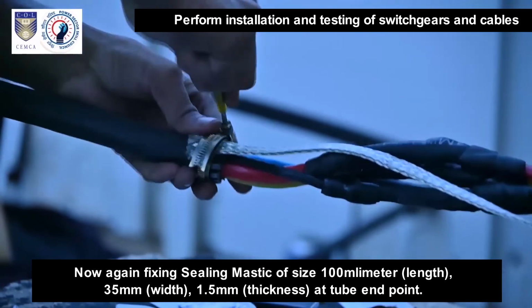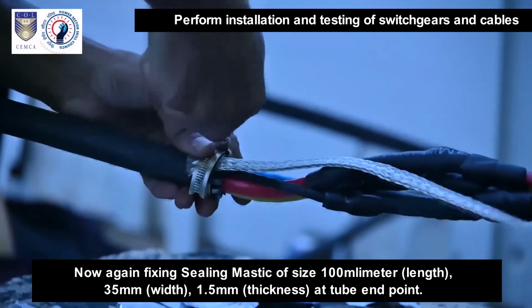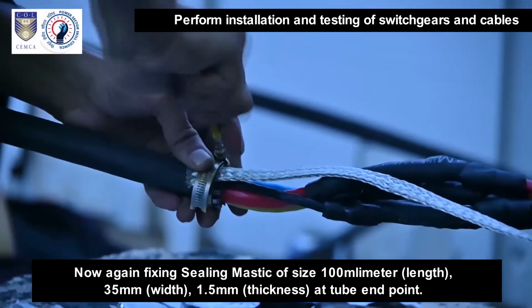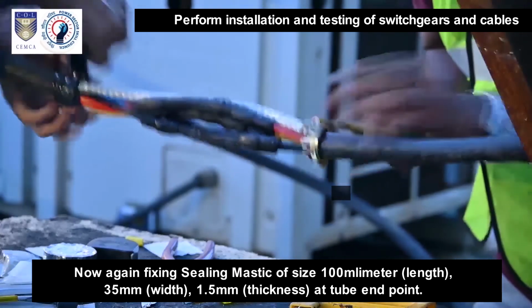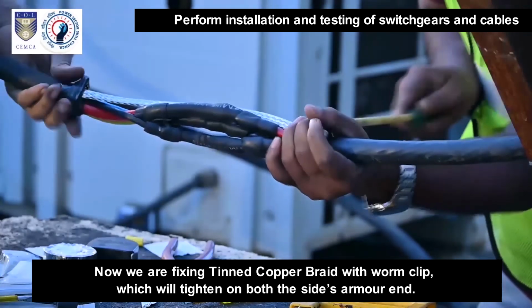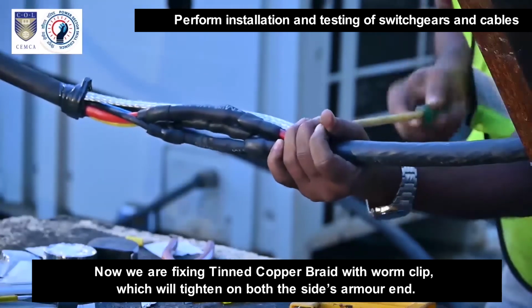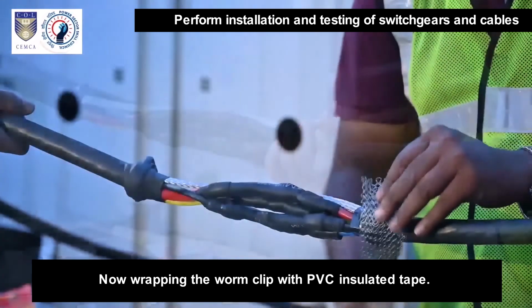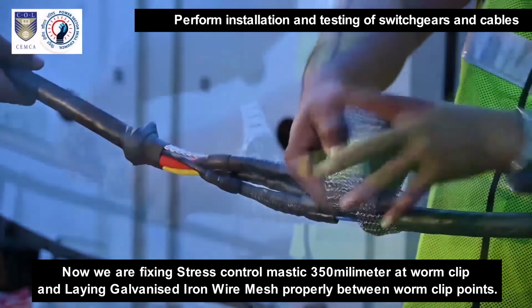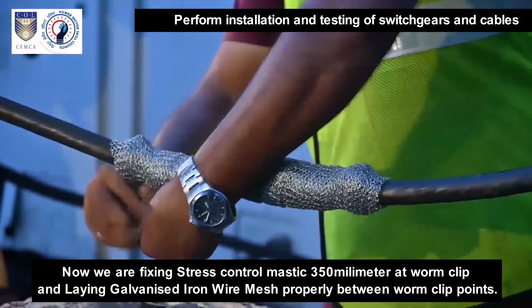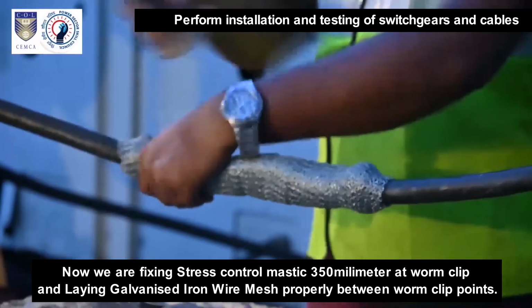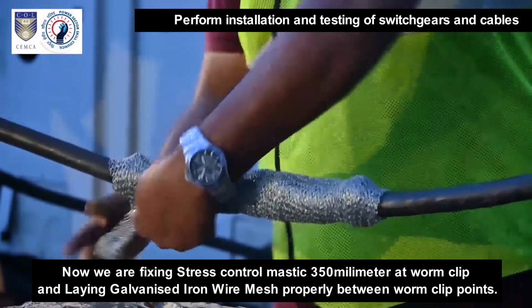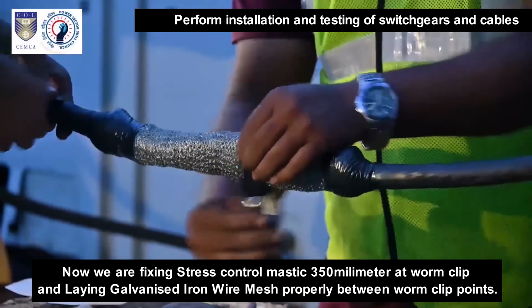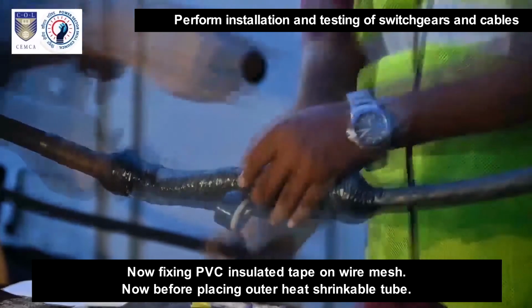Again fixing sealing mastic of size 100 mm length, 35 mm width, 1.5 mm thickness at the tube end point. Now we are fixing tinned copper braid with a worm clip, which will tighten on both sides at the armor end. Now wrapping the worm clip with PVC insulated tape. Now we are fixing stress control mastic 350 mm at the worm clip and laying galvanized iron wire mesh properly between the worm clip points. Now fixing PVC insulated tape on the wire mesh.